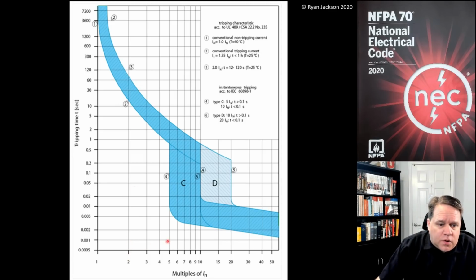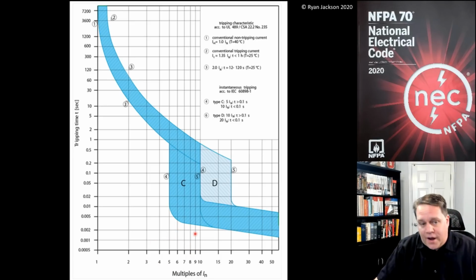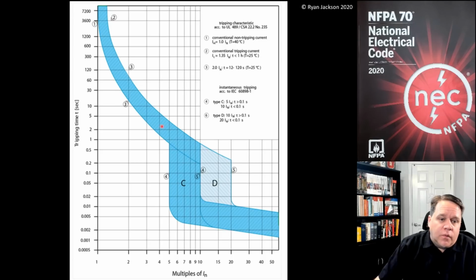So what if I put 5 times the rating of that circuit breaker, which would be 100 amps? Well, now we can see that we've left the thermal part of the breaker and we've gotten into the magnetic part of the breaker. And that's when it's going to open very quickly.